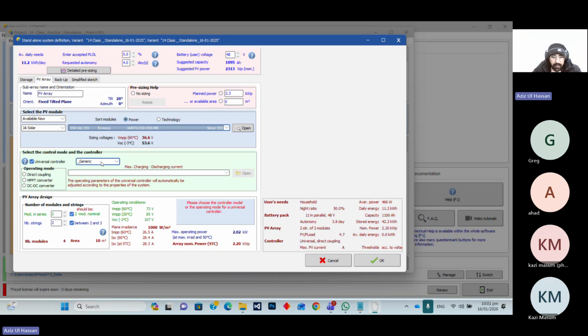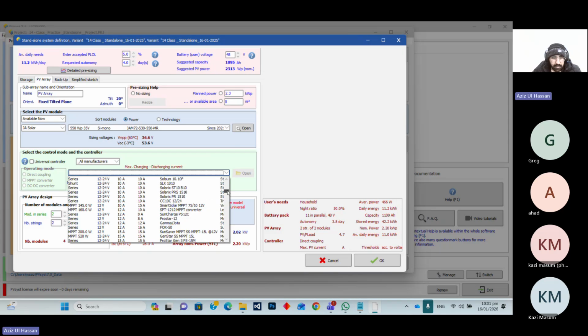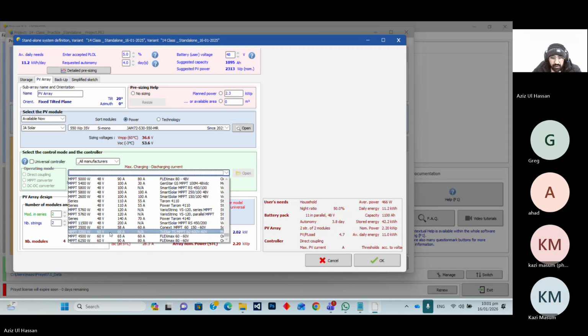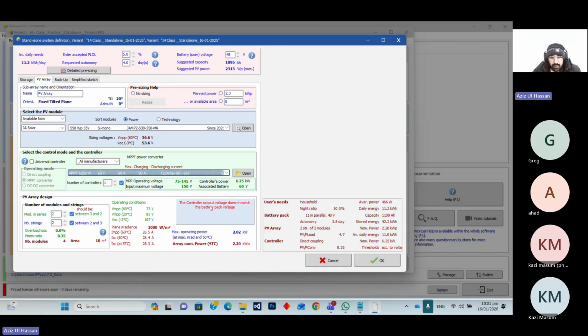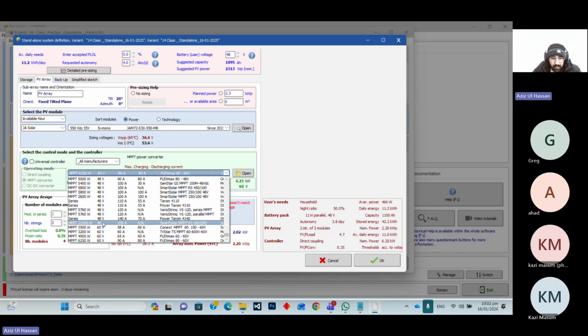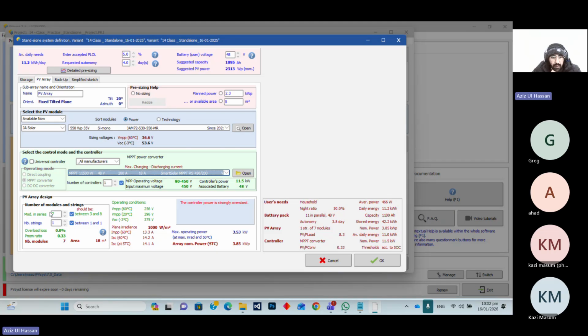Now you have to select the controller, all manufacturers. Like we have that one, MPPT controller, 60 volt, 3.5. The controller output voltage does not match the battery package. So we have to select 48 volt. This one is oversized, so we have to select that one. Like we have to select 8 PV modules, and the number of strings we have selected like 10.